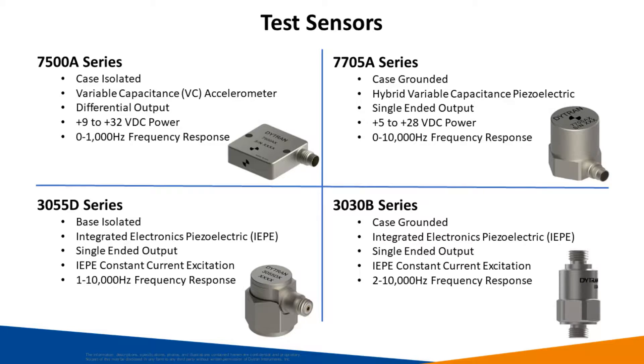For this test, four sensors were selected. The 7500 series is a case isolated variable capacitance accelerometer. This unit has a differential output and requires an excitation of 9 volts to 32 volts DC. It has a frequency response from 0 Hz to 1 kHz. The 3055 series is a base isolated integrated electronic piezoelectric accelerometer. It has a single-ended output and requires an IEPE constant current excitation. It has a frequency response from 1 Hz to 10 kHz.